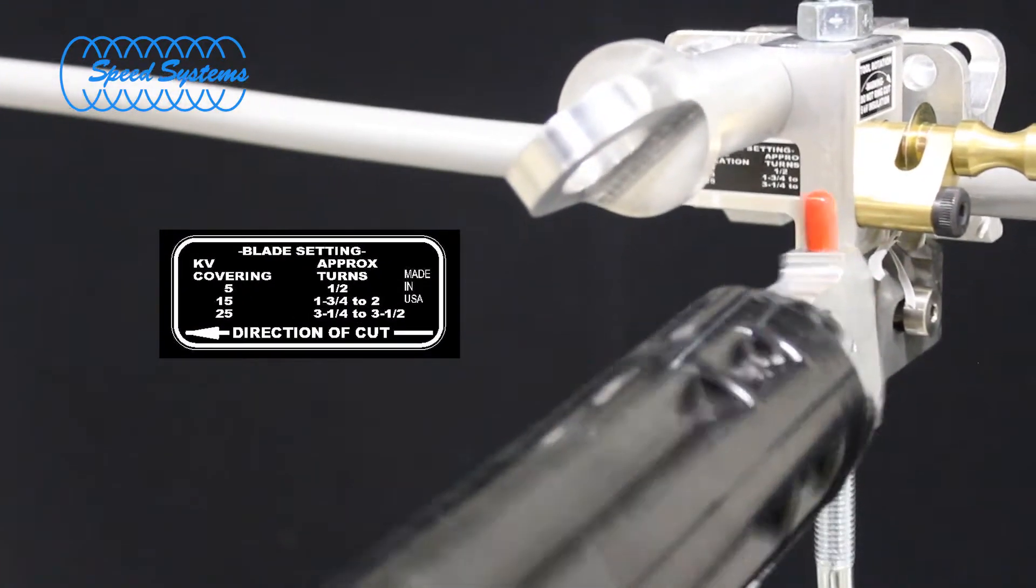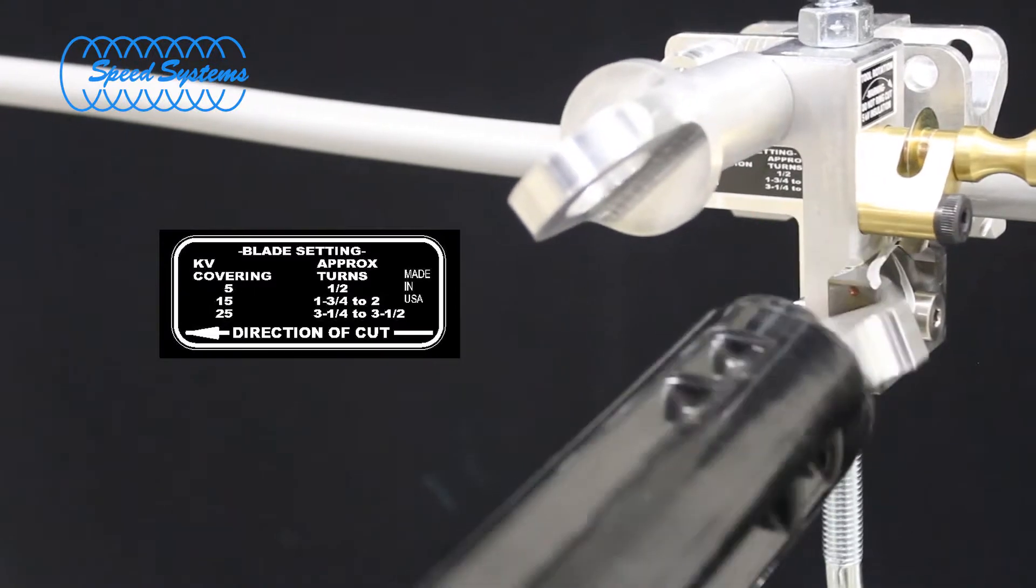Move the stick to the blade adjuster eye and set the blade depth. Use the chart on the nameplate as a guide to the approximate blade depth setting based on the kV rating of the cable.